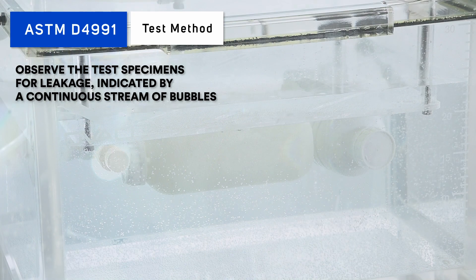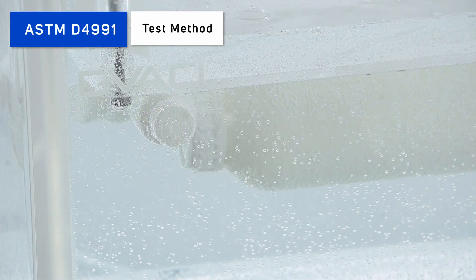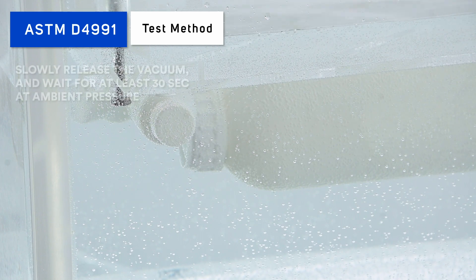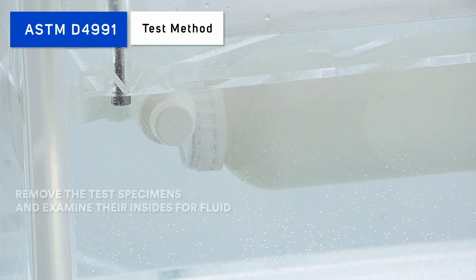Carefully observe the test specimens for leakage indicated by a continuous stream of bubbles. Maintain the vacuum for the required time, then slowly release it and wait for at least 30 seconds at ambient pressure, before removing the test specimens and checking if there is any fluid inside them.